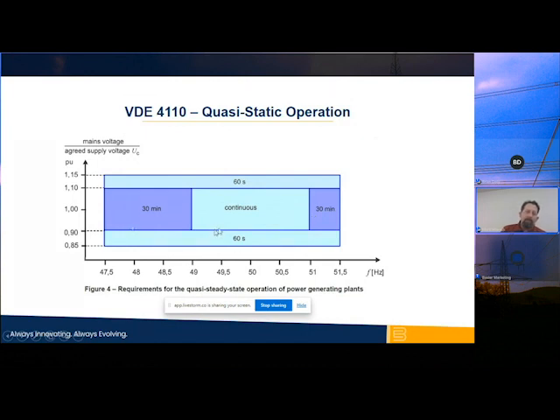As soon as these conditions are crossed, the disconnect and reconnect capabilities of the voltage regulator can start to time. Once we get outside of these borders, there's a condition at hand, and the voltage regulator is going to have to support it. This is where I get into what I call low voltage ride through conditions. I'm going to time those conditions and try to stay online. I have to keep that machine online for whatever that set time delay is. As soon as I cross that threshold, I start to time. If I stay below that threshold after 60 seconds, then I disconnect.